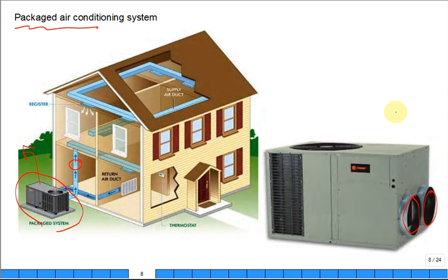No, I would say sometimes people will get a contractor to come out, and say, well, your furnace is in pretty good condition, but your condensing unit's bad. Well, just replace that because I don't have the money to pay for both. And then they start to get mismatch. They got like a 5-ton unit on the outside and a 4-ton furnace, and it's a mismatch. But here you don't have that mismatch. It's all packaged.